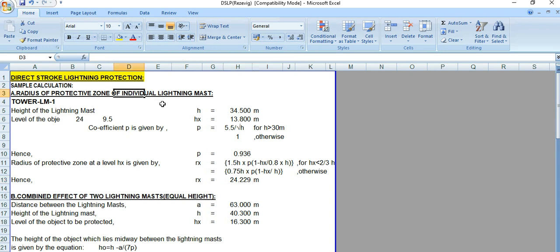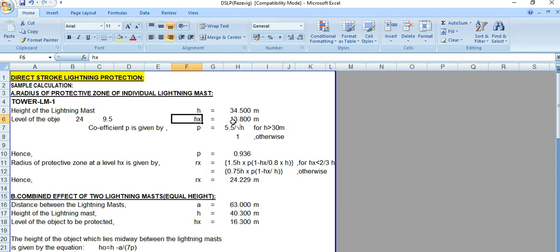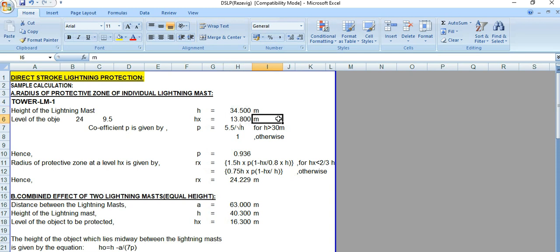This result is applicable for an individual lightning mast. Wherever there is a standalone lightning mast and outdoor equipment, we can protect objects that are not at ground level. Here hx means the peak of the object to be protected is at 13.8 meters. The effective height of the lightning mast is essentially h minus hx, that is 34.5 minus 13.8 meters. In this video we discussed direct stroke lightning protection for an individual lightning mast.